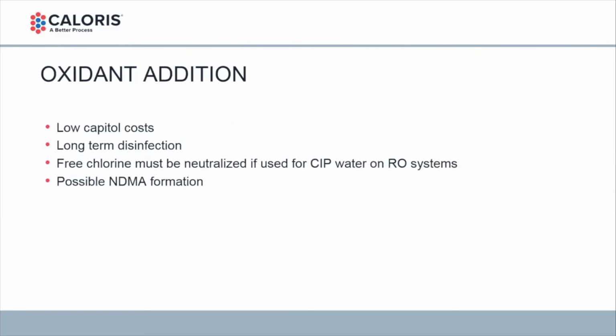Okay, oxidant addition, by far the lowest capital cost. It does have long-term disinfection. But the problem with chlorine is that a lot of plants don't want chlorine in their plants. An issue is if you use free chlorine for CIP on an RO system, you need to neutralize that chlorine before you use it, or you'll quickly destroy your RO membranes.